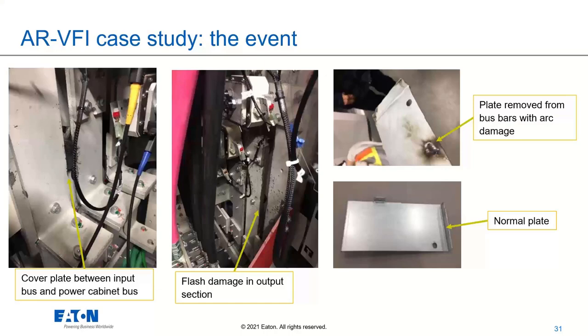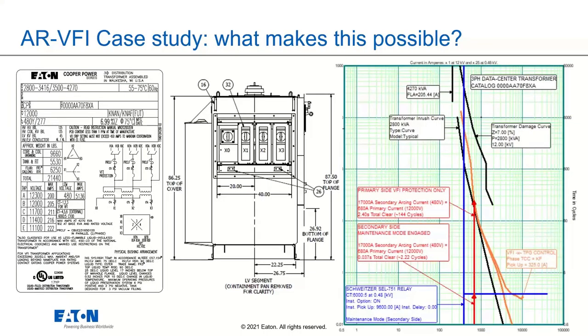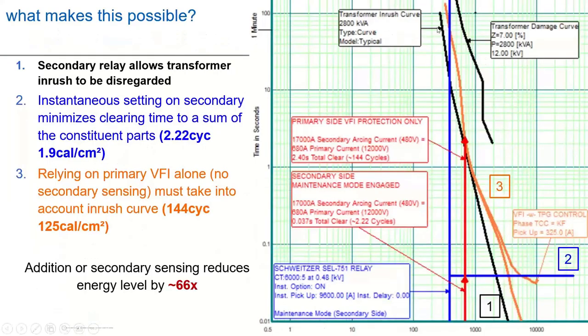So what I really want to highlight here is the TCC on this. And I mentioned this a little bit before, but that transformer inrush curve, that black line. If we're comparing just a primary side breaker setting, so the same exact breaker, still that two cycle VFI breaker, it's about as tight as you can get without crossing that inrush threshold. I don't want a nuisance operation on startup, but I want to be as protected as I can. If I'm looking at that orange line, I'm at about 144 cycles, 125 calories if I have my primary device alone. Again, well over where that 40 calorie cutoff is going to be.